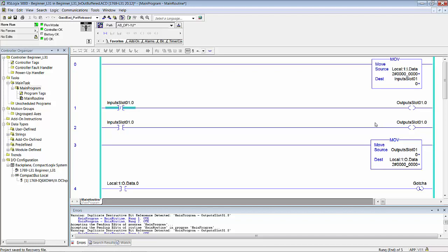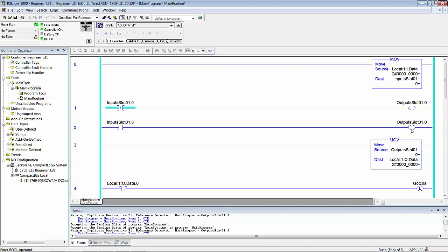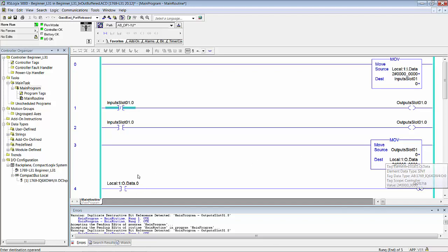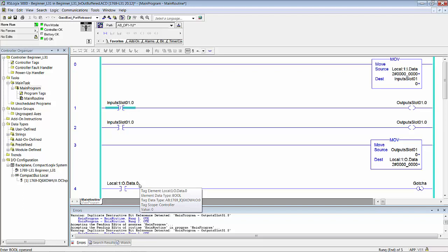Remember I told you this rung is true, turns that bit on; this rung is false, turns that bit off. So guess what? This graphical user interface, RSLogix 5000, is looking at the data table. It's not looking at the code. This ladder logic you see here, that's a figment of our imagination. It only exists to present a relationship of the data with the machine-level language that's in there executing the code right now. We are actually looking directly at that bit in memory. We're not looking at the result of the logic. So this is something definitely to keep in mind, and this proves that point emphatically: when you see this change state, it's changing state in memory, but it's not going from the memory out to this word and then out to the output device. Otherwise, remember that this is Local:1:O.Data, this is Local:1:O.Data bit zero. If this were to be true it would latch that bit on and it would stay on. I don't have an unlatch anywhere. Very interesting.